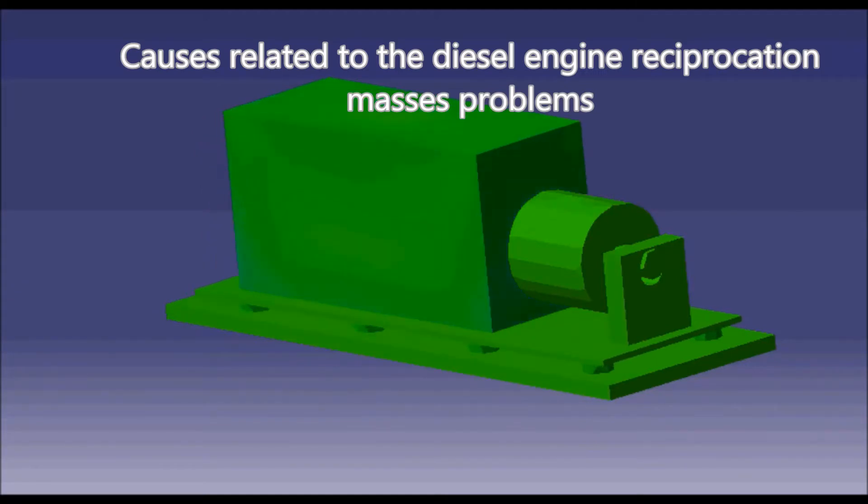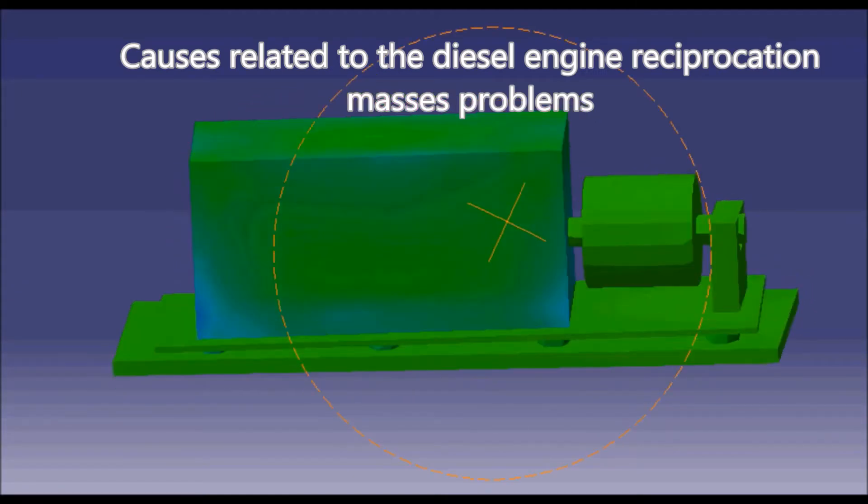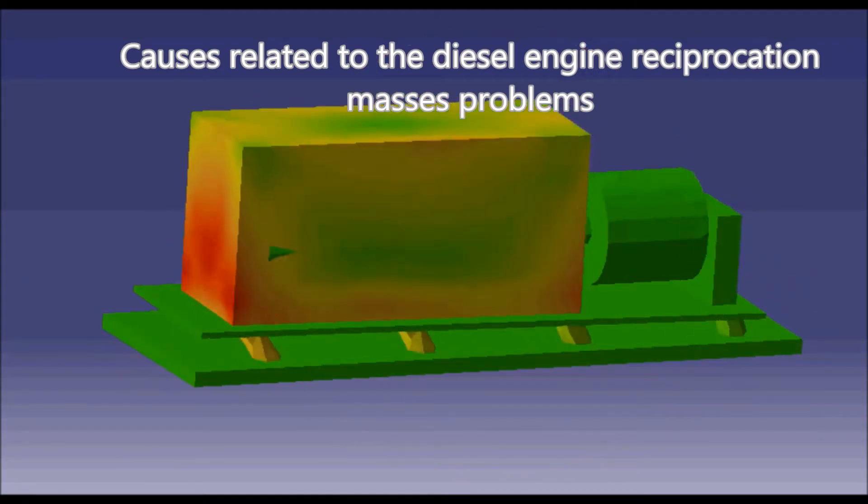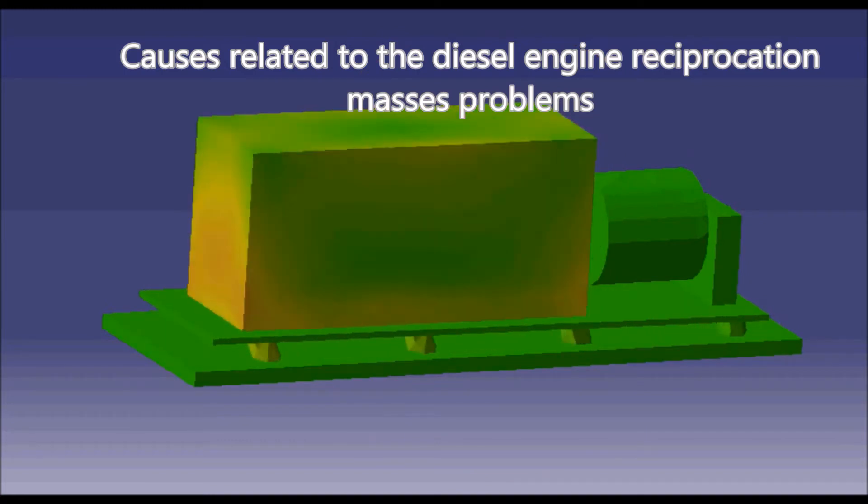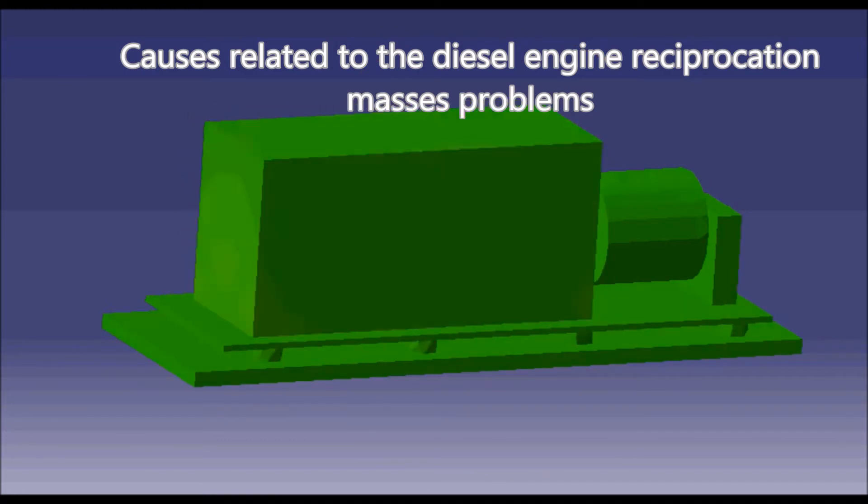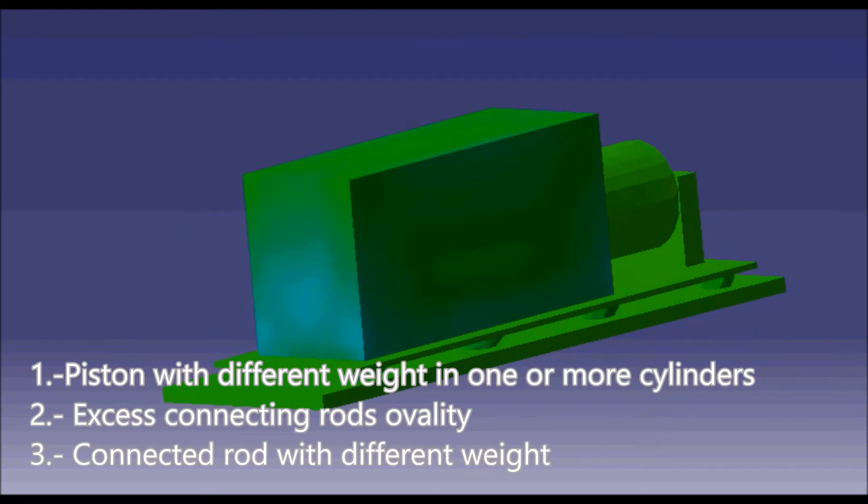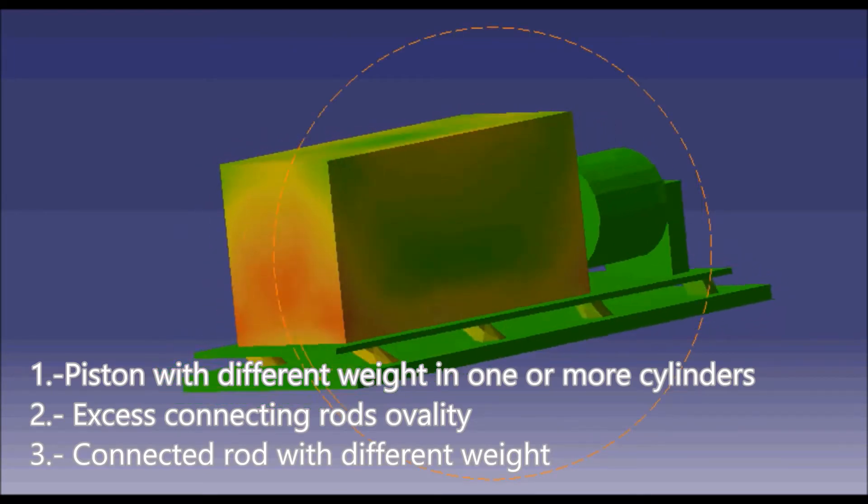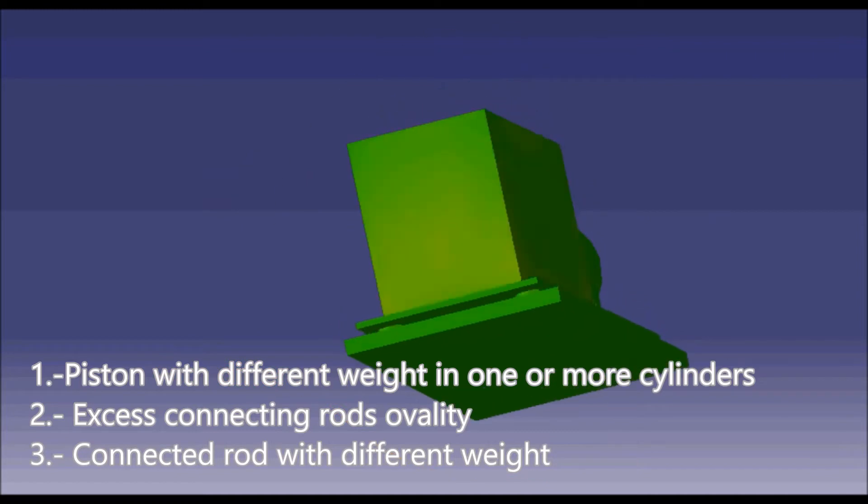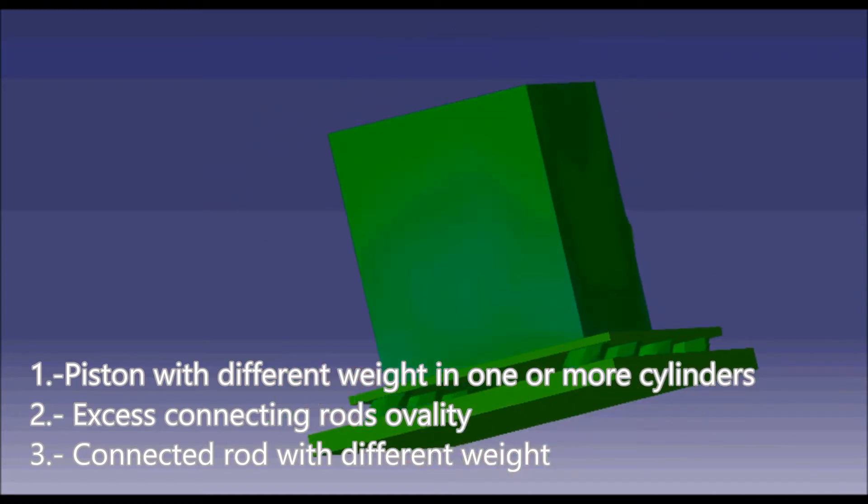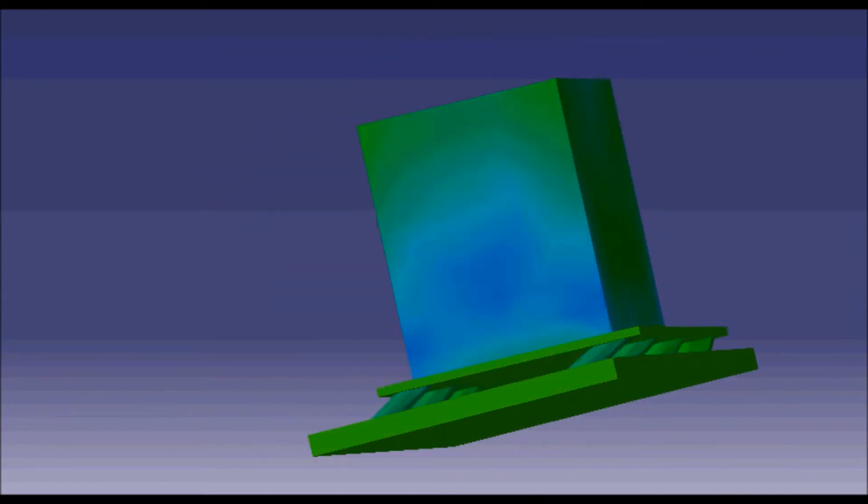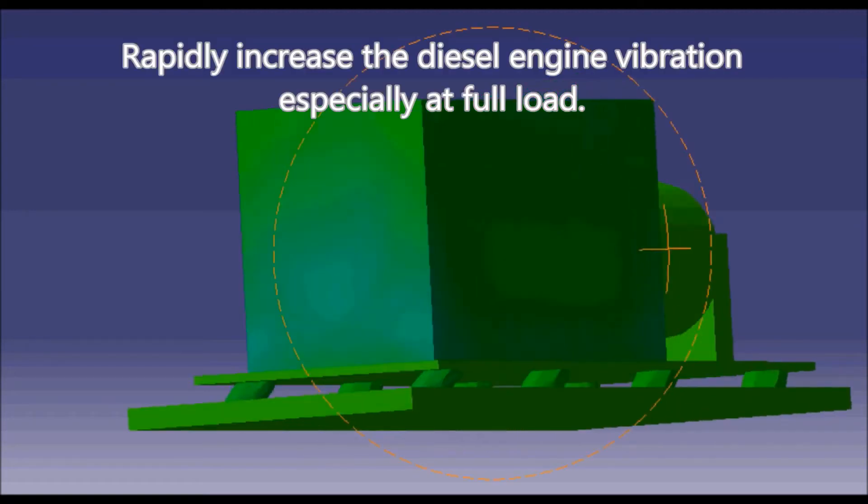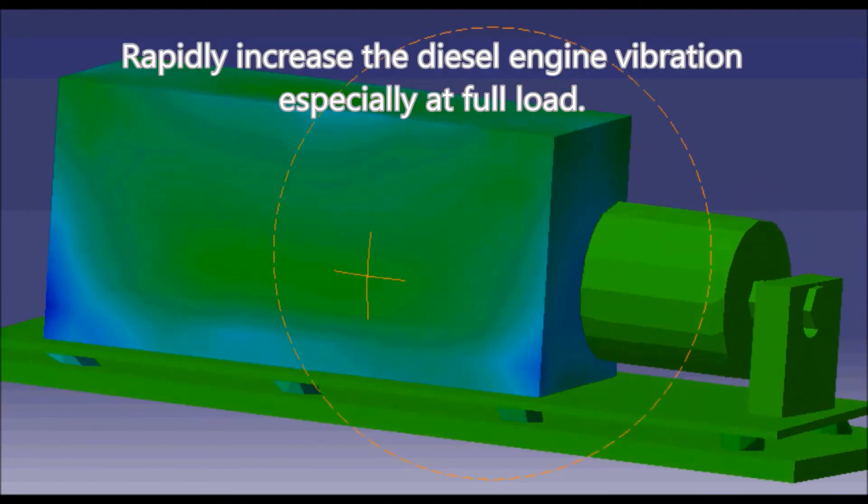Causes related to the diesel engine reciprocation masses problems: 1) piston with different weight in one or more cylinders, 2) excess connecting rod ovality, 3) connecting rod with different weight. These rapidly increase the diesel engine vibration, especially at full load.